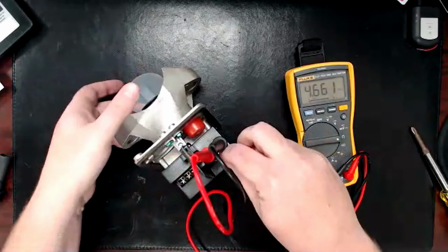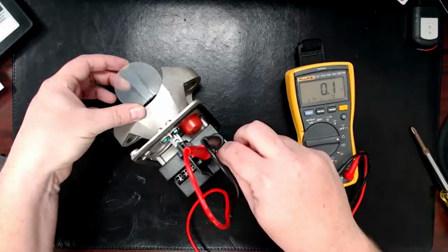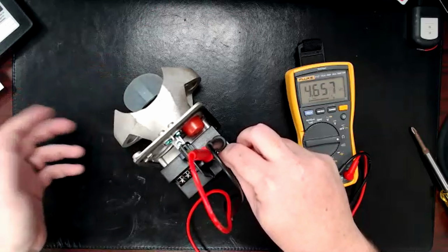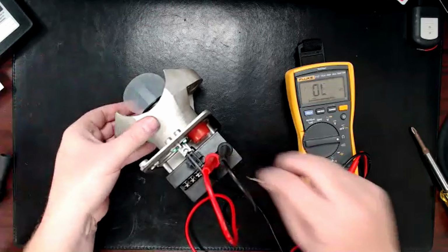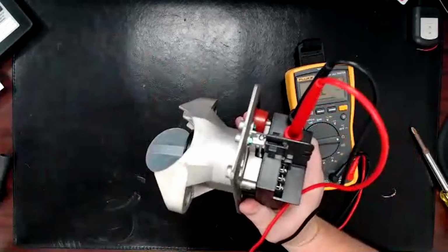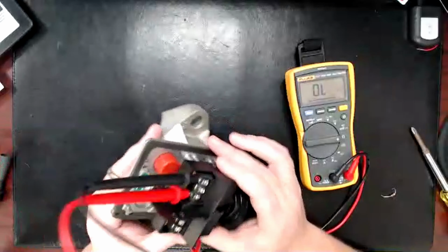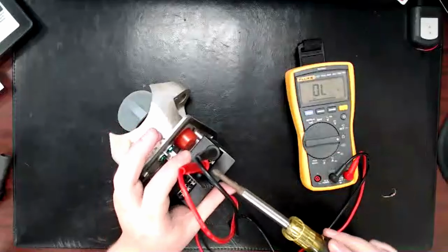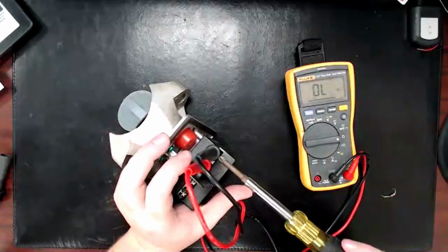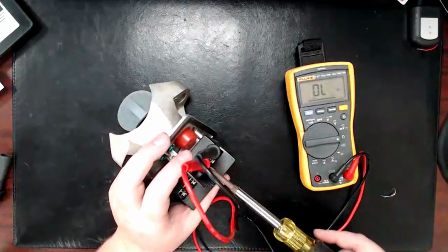So there's that 4.6. And then if I move this paddle, see, I have no time delay. So it goes right to that alarm. And I let go of it. So there's nothing that's going to actually have to be set or adjusted, like that other valve, except for this timer. And the point of the timer is going to be water pressure. So city pressure, especially, I'm going to leave this on here actually, because the next part will still use that.